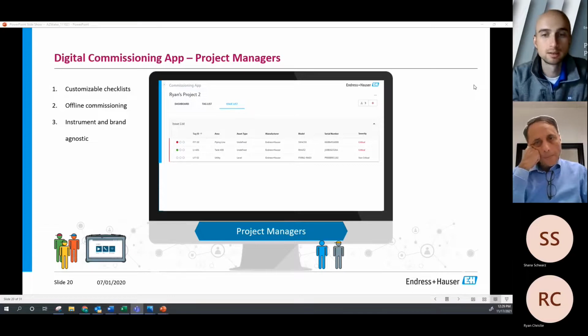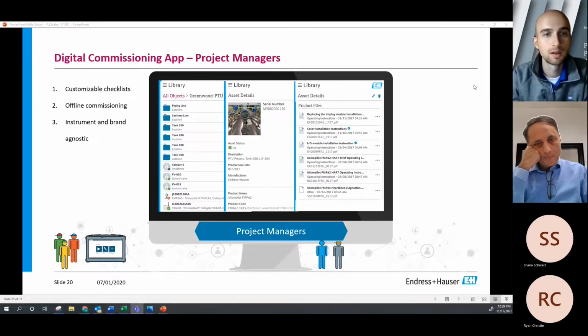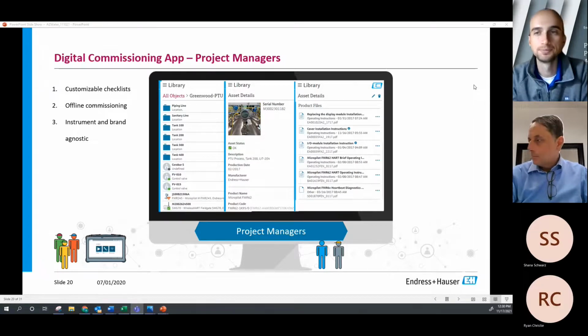Another part of that is the library function within the app. You could quickly see or have access to all the startup and commissioning documents required—an as-found and as-left calibration, say for a pressure transmitter, or a verification report for a flow meter. All of that can be stored within this digital commissioning app so that when it eventually gets handed over, it's already all combined in a nice, neat package for you.